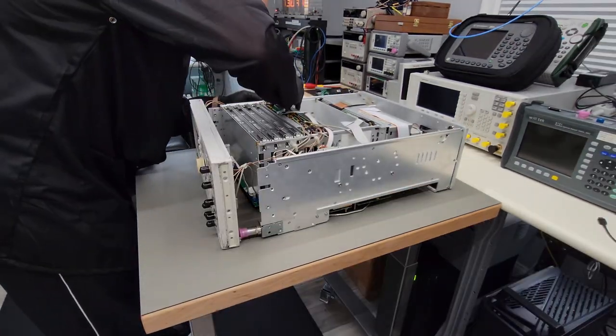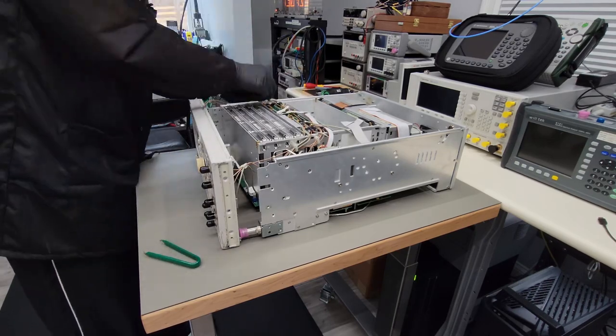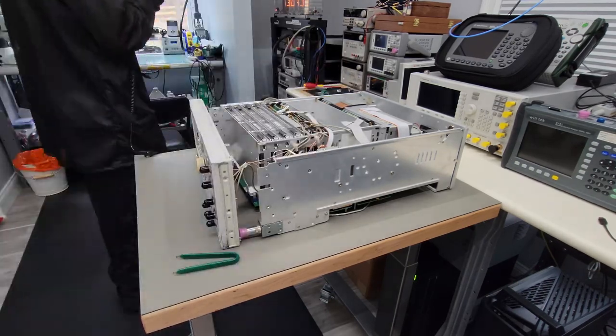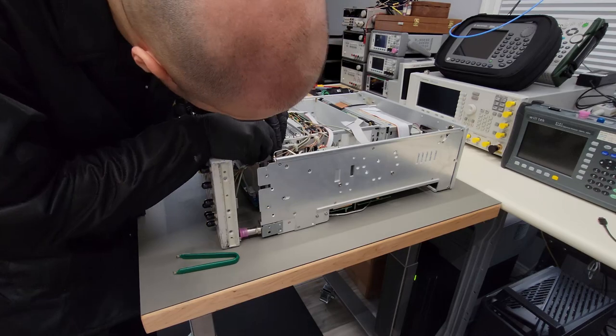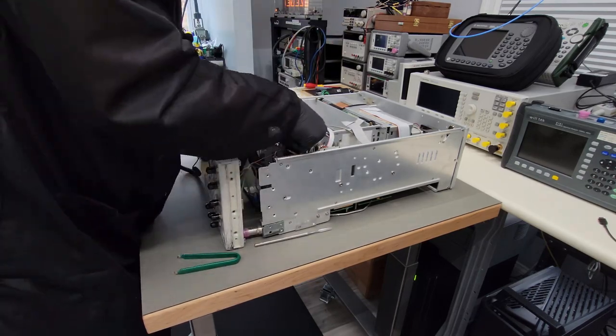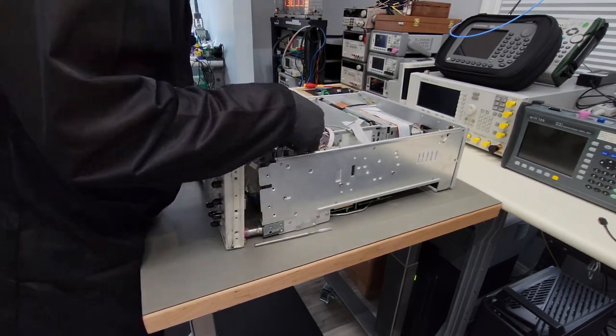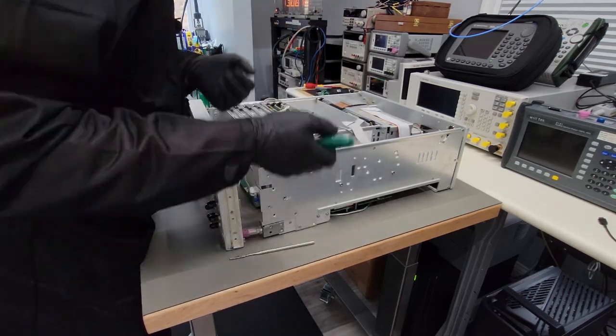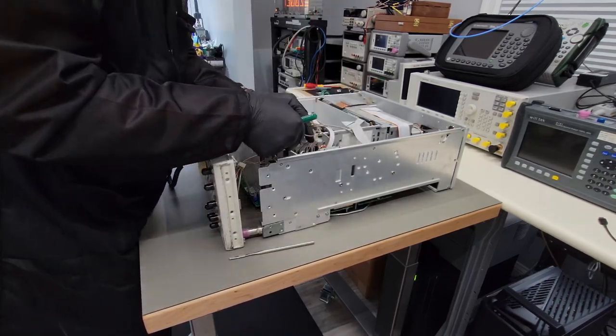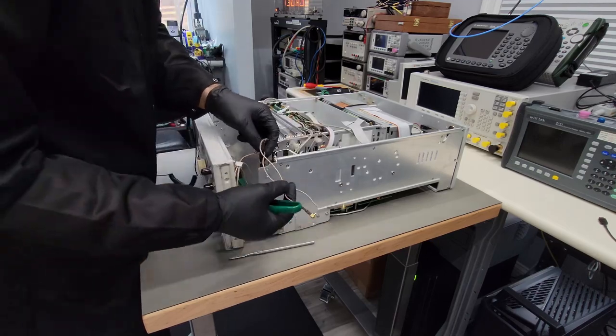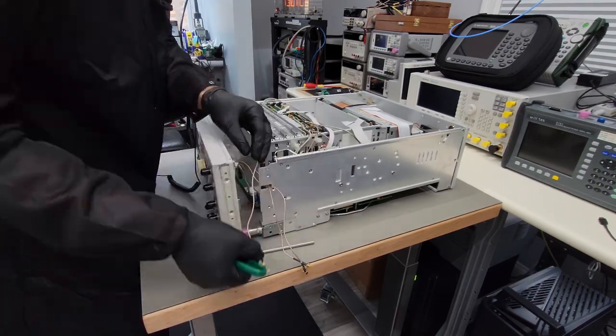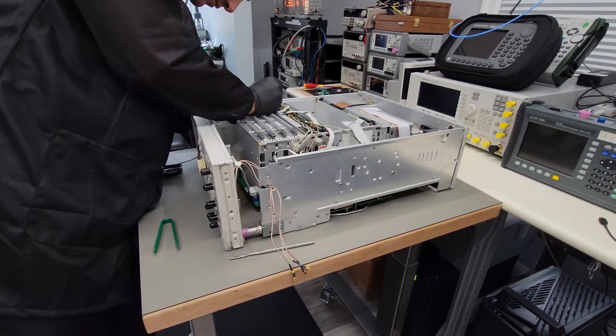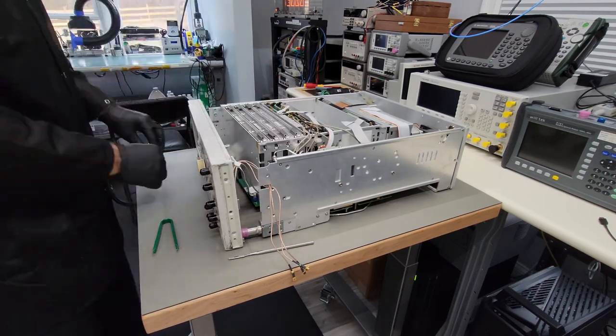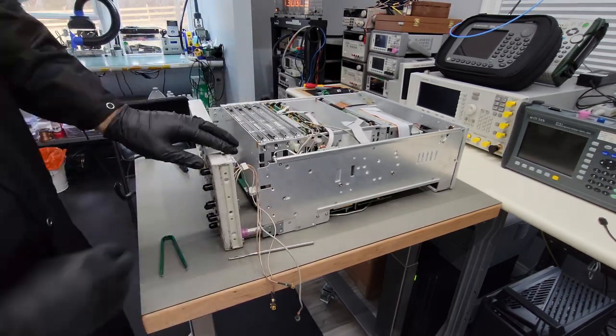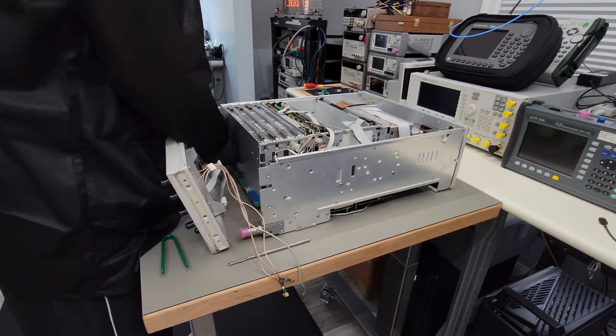So in order to completely separate the front panel from the instrument, there are a number of cables that need to be removed from the inside, coaxial cables that connect to various boards. So just got to take your time here and separate everything, and then unplug the digital connectors as well. Make sure you label everything so you can put it back together in the correct order. And then we can get the front panel out of the way so we can assess the mechanical damage to the front panel connector itself and begin to make that repair.